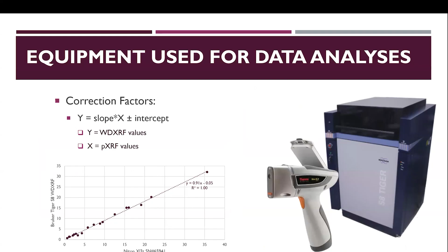The comparison between the results of the two equipment on this kit established by the network has helped with the calculation of correction factors that might be applied as a first step in the intercalibration of portable data, to be closer to WD values for the problematic of data accuracy. This ceramic disc kit was not only used for the assessment of the portable equipment accuracy and precision, but also for the device factory calibration and stability.